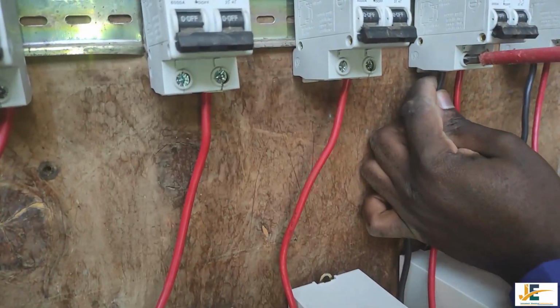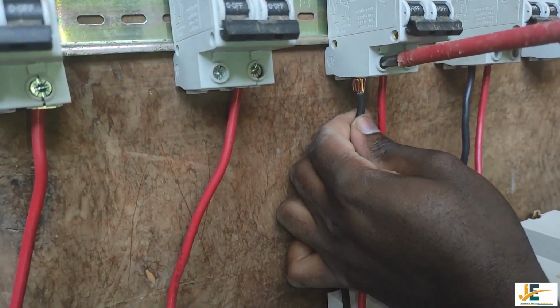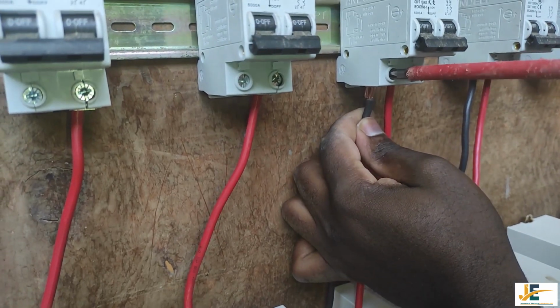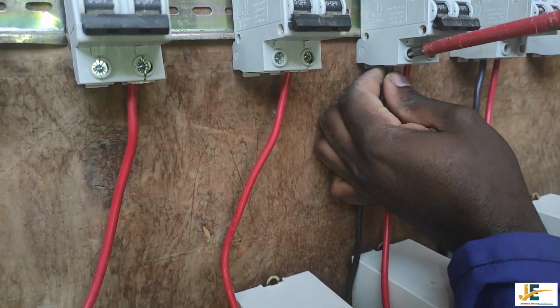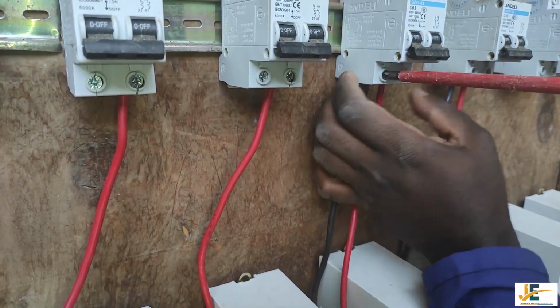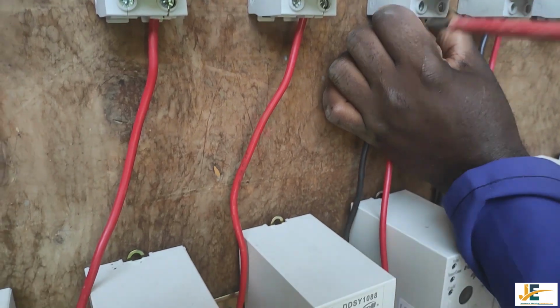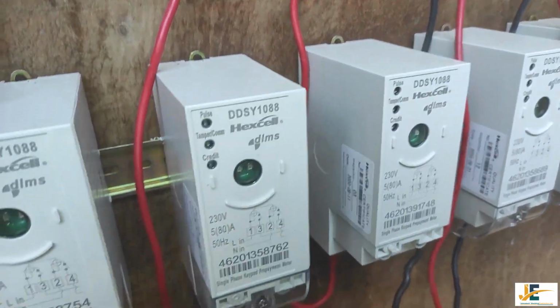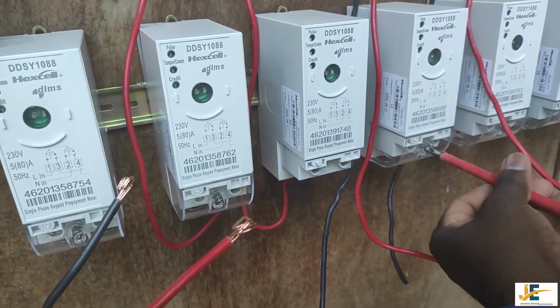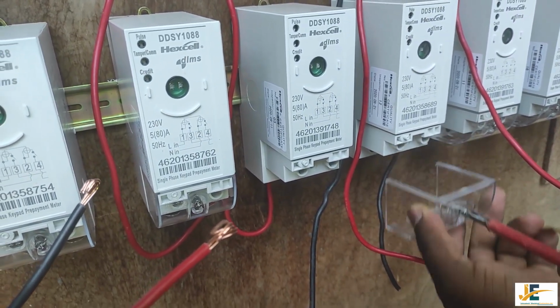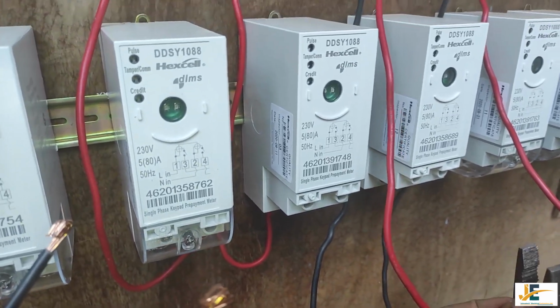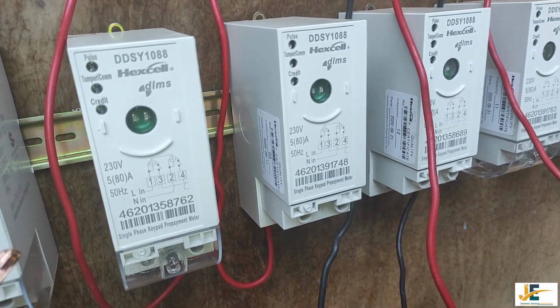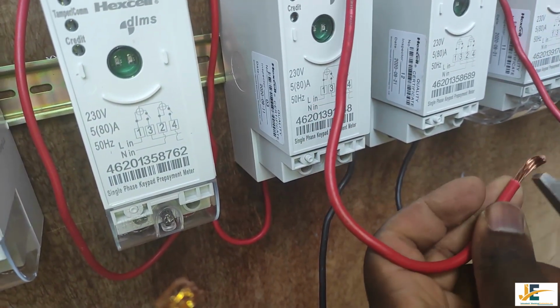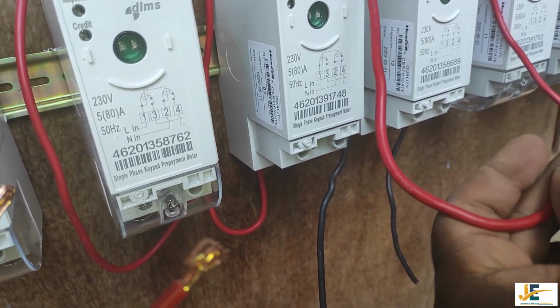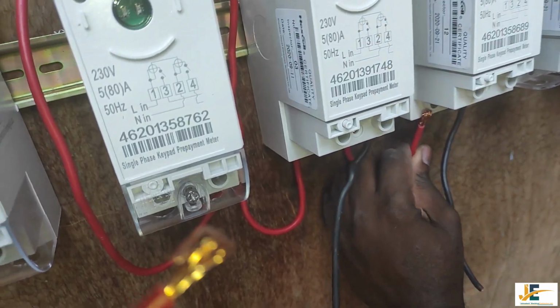Once you are done with the mounting of double poles, then you can mount the MCUs or the meters. These meters, for you to mount them, is tricky. You're not supposed to mount the DIN rail for the meters first. Otherwise, for this model of the meter, if you do so, it's going to give you a very hard time. So you make sure that you fix the meters first before you screw or mount the DIN rail. Once you fix them all, then you can mount the DIN rail together with the meters.